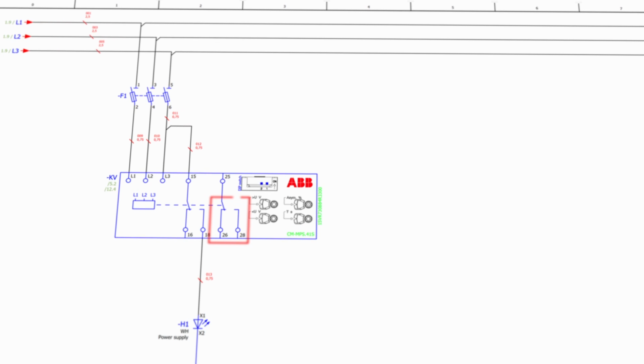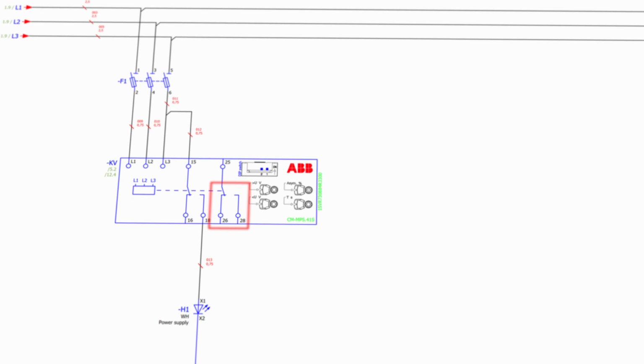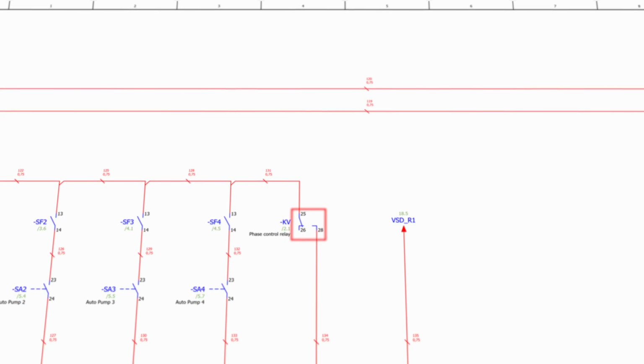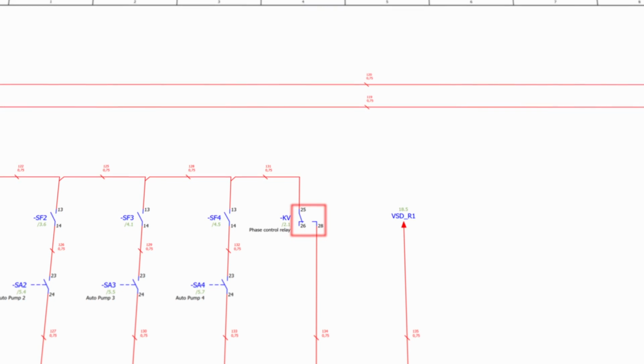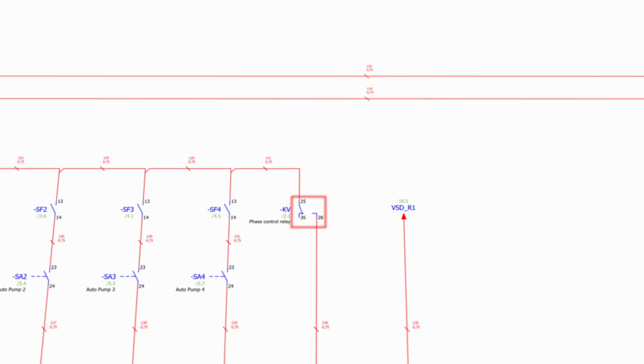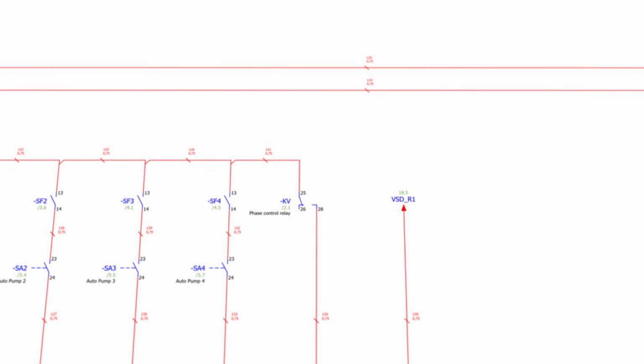Now the question is, why do we need to do something with the signal that is just coming from supply network control relay? If we look at the schematics, we can see that relay has a switchover contact. And although schematics says to connect wire to normally open terminal, practice shows that it could be a major source of confusion between electricians and programmers.